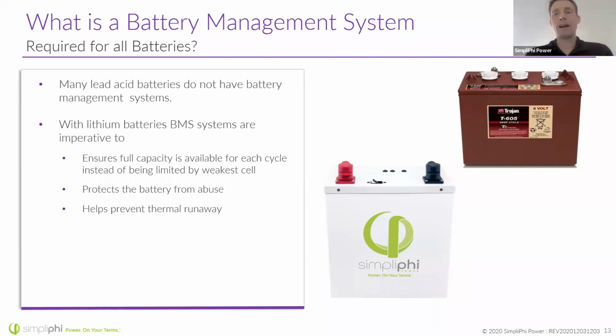Lead acid batteries are often rated at a C/20 discharge rate, meaning if you slowly discharged the battery over 20 hours, that's how much total energy you'd get out of it. The faster you take energy out of a battery, the more energy you lose as heat. Most lead acid batteries shouldn't be discharged below a 50% state of charge, so their rated capacities are really a little misleading.